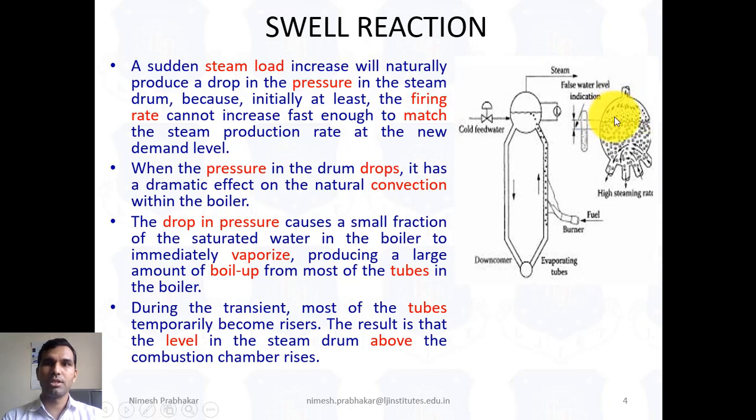of water inside this tank, indicates a false water level because of the presence of these bubbles over the water. So this effect is known as swelling or the swell reaction. In the swell, the indicator indicates the wrong or false level, because the actual level is this, but due to the presence of these bubbles, the level indicator gives the wrong reading. So this effect is known as the swelling effect.